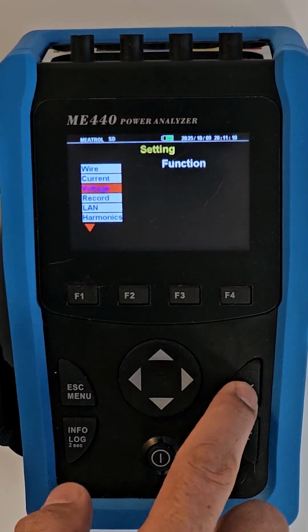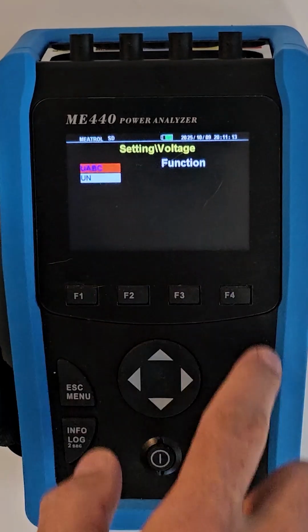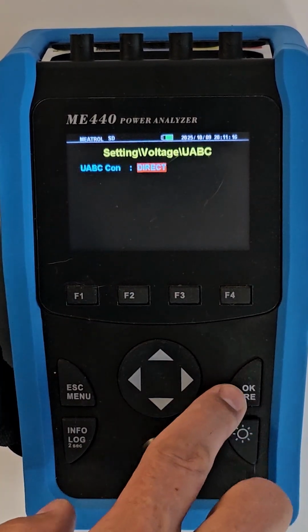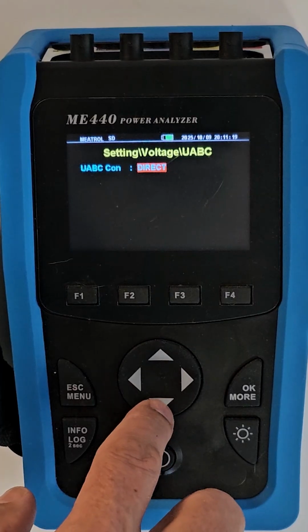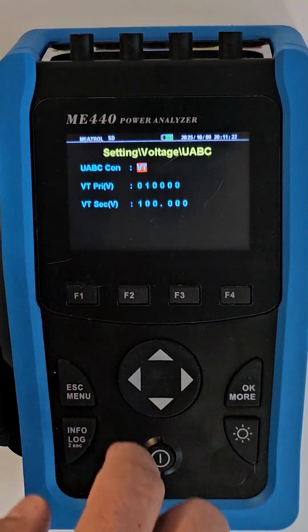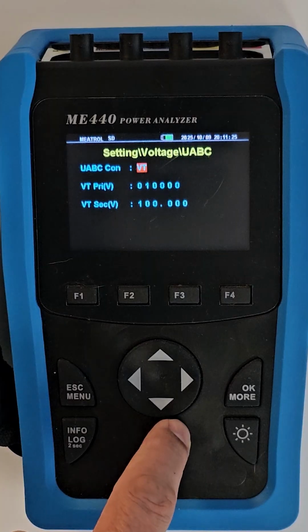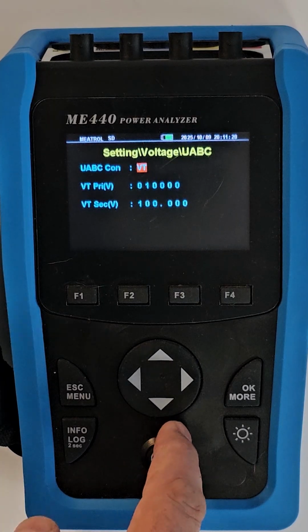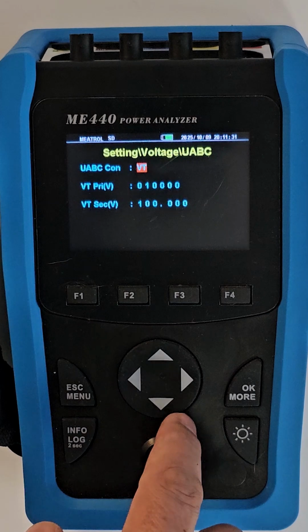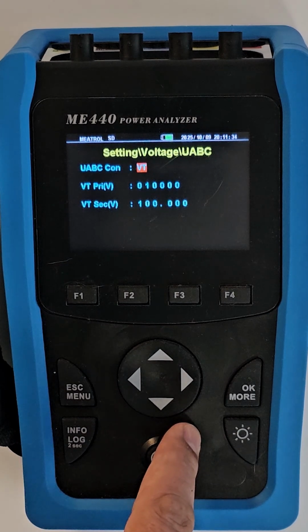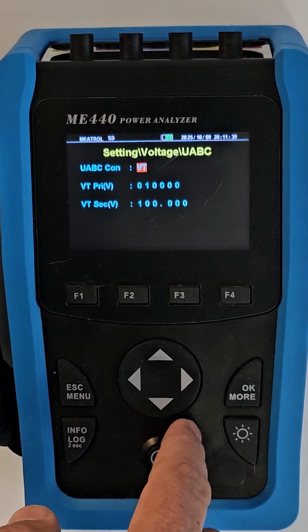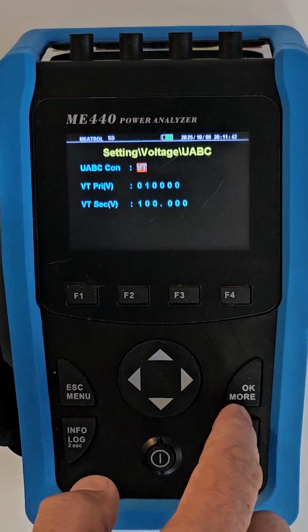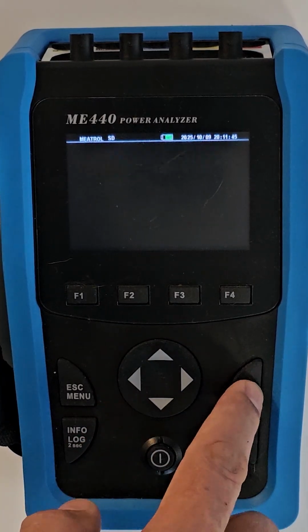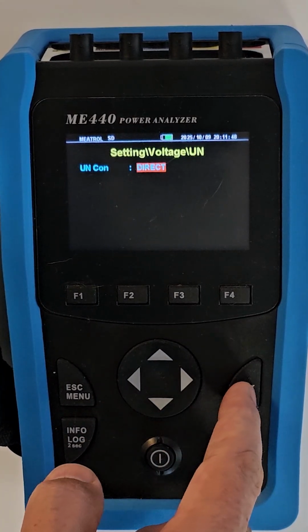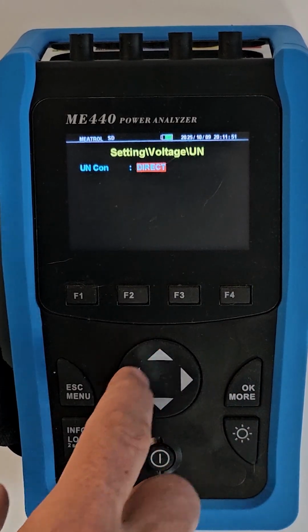Okay, so if you continue to the voltage menu, you can see here you can set the voltage for phase ABC 1, 2, 3, and it can either be direct or VT, stands for voltage transformer. And then if you want to measure high voltage, you can set a ratio here to get it down to the correct voltage. The maximum input voltage for the meter is 480 volts AC, phase to neutral. So let's just change that back to direct connection. And then you can also set the same for the neutral conductor, either direct or voltage transformer.